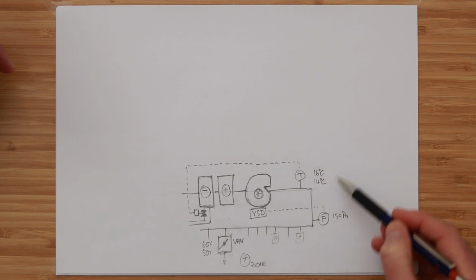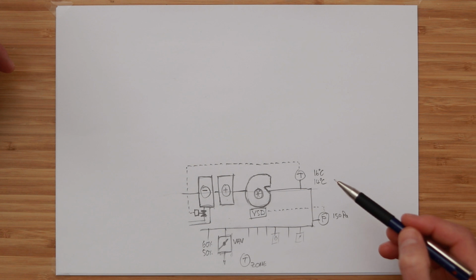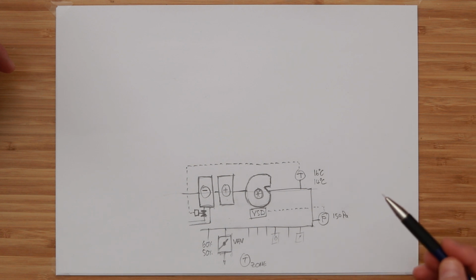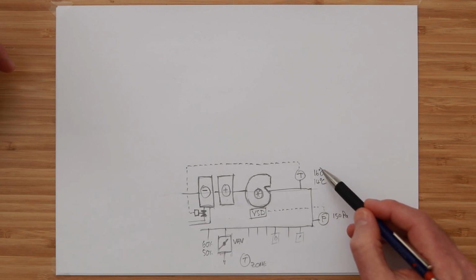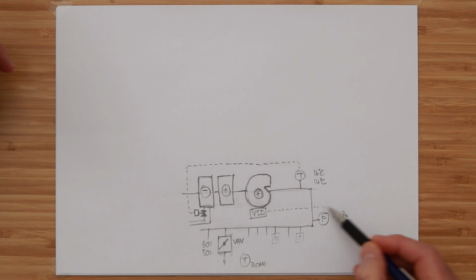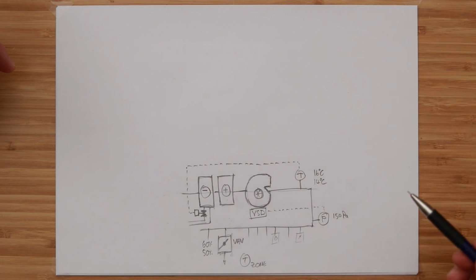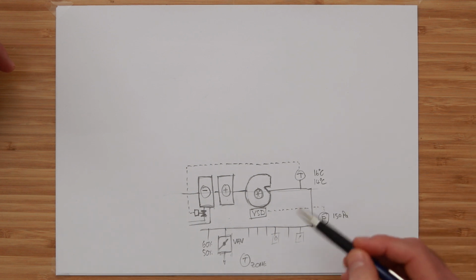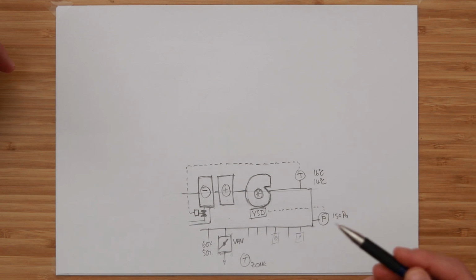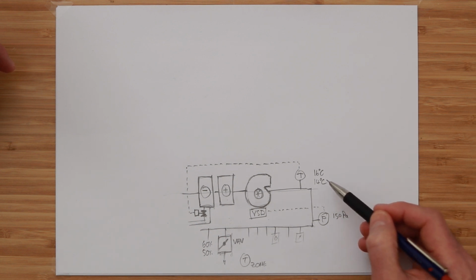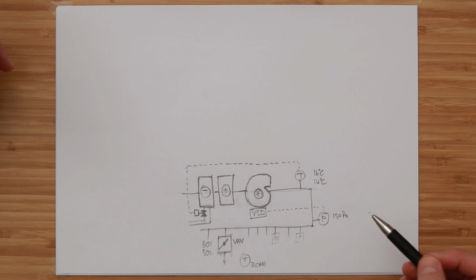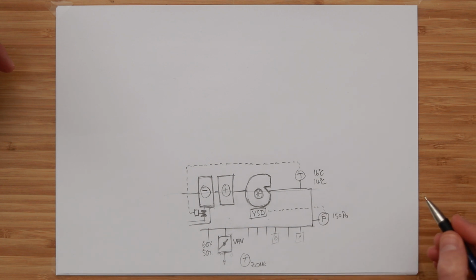So there's a reasonably complex control strategy around trying to manipulate the speed of response of the supply air temperature reset against the supply air pressure reset to try and slightly bias a slightly cooler air, which results in the fan slowing down. So by manipulating our control strategy and through our energy efficiency optimization tuning, we can get all of our air handling unit fans to slow down slightly by reducing the supply air temperature slightly.